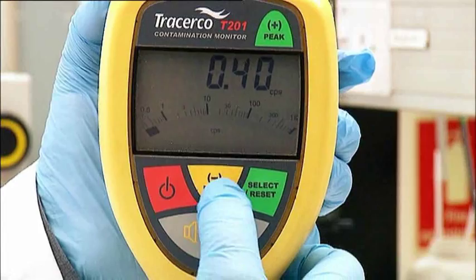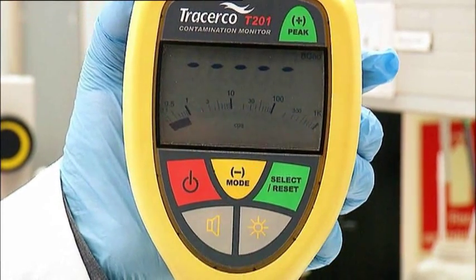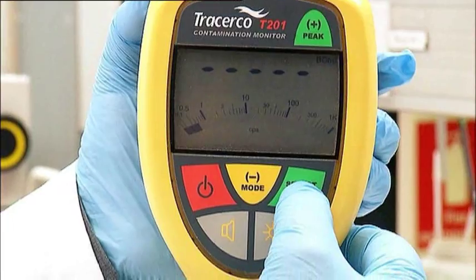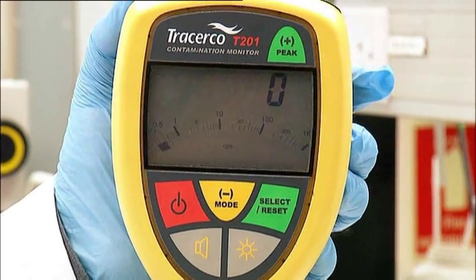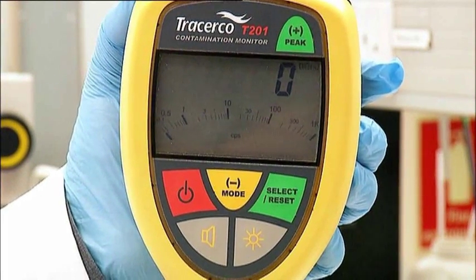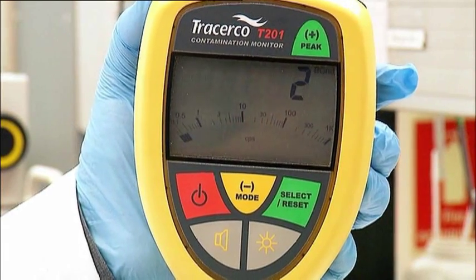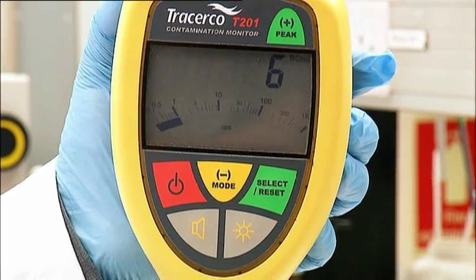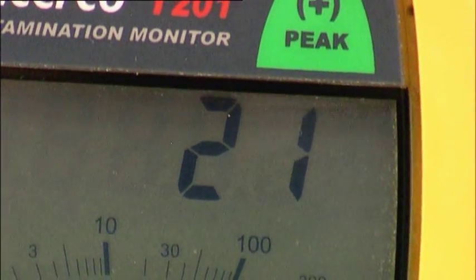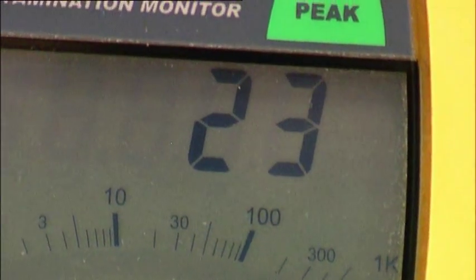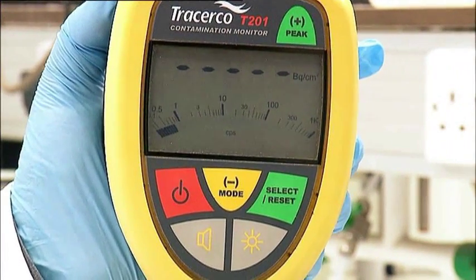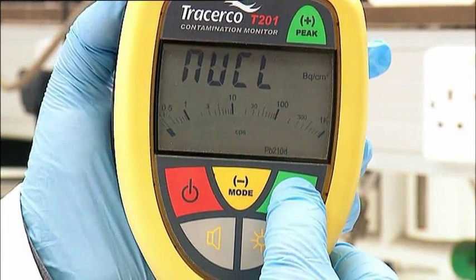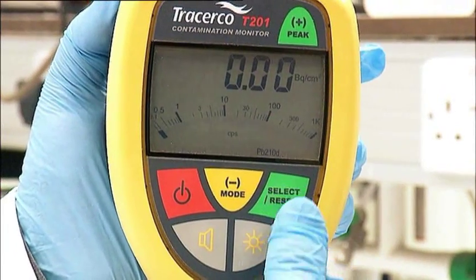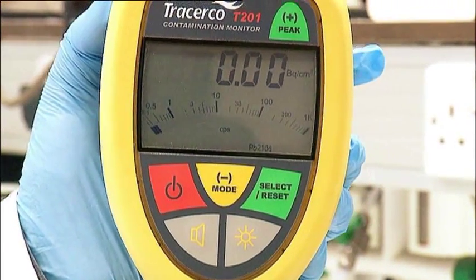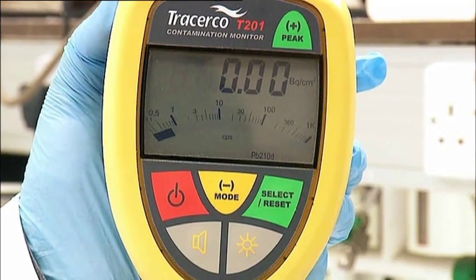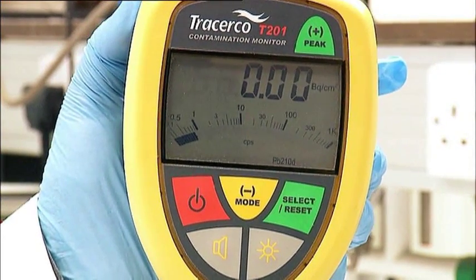Press the Mode button, and when the background message appears on the screen, the Select Reset button should be pressed. The monitor will automatically commence a 60-second background count. After this, the display will show the mean background count in counts per second, and this value will be automatically stored in memory. Press Select Reset to accept this count and move to the becquerels per centimetre squared screen. This background count will remain in memory after the monitor has been switched off, and the value will only be updated when the background count is repeated.